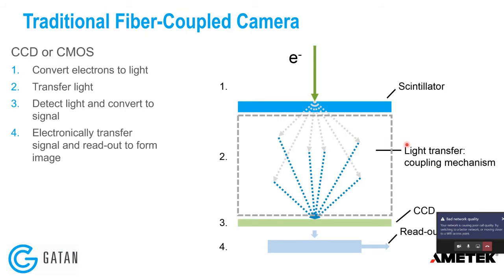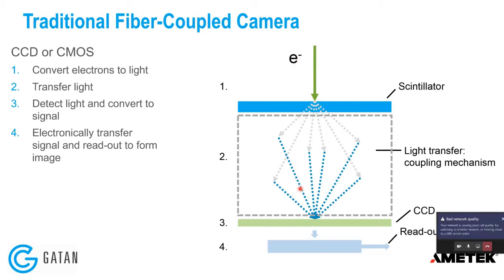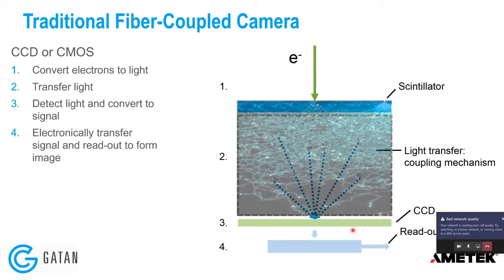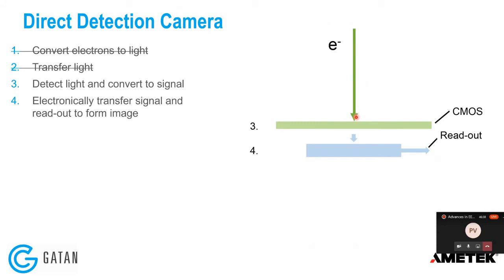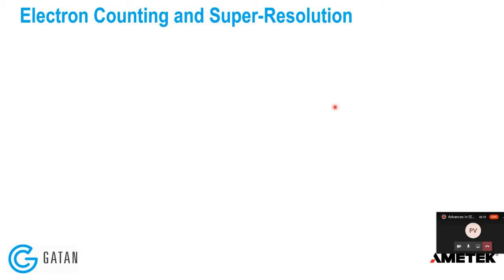In traditional fiber-coupled cameras there is quite a lot of scattering, which hurts resolution. In direct detection, everything is nicely confined and the sensor is exposed straight to the electrons, greatly improving resolution. The key technique applied here is called counting. When an electron strikes a pixel it generates charge spread over neighboring pixels. You can read out all the charge (accumulation mode), or you can measure the center of gravity of the electron — finding that about 75% of the charge produced is localized in specific pixels — and assign the entire event to one electron. This dramatically improves image quality and reduces noise.